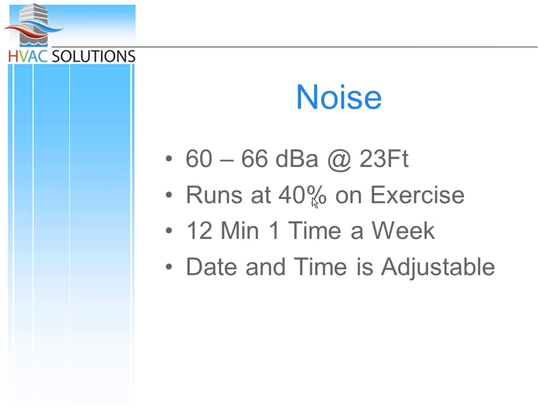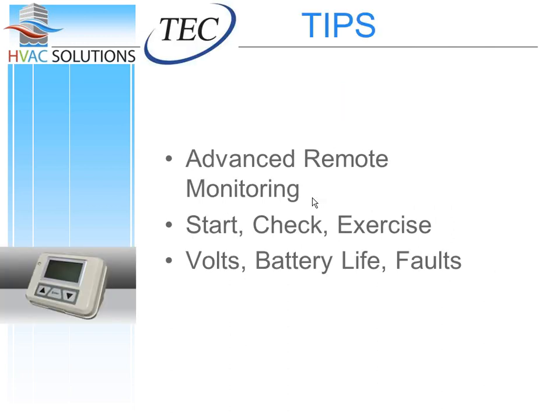When we talk about the noise, I'll tell you, these things sound like a riding lawnmower. They are not quiet. The nice thing is that when they exercise, which is once a week for about 12 minutes, they run at about half capacity, so it's not full blown - it's running at a lower RPM, and you can have it come on when you'd like. It doesn't have to be Sunday at 2 in the morning, you can have it Saturday morning at 10, something like that. So I talked about the 6 different features that make this unit different from what the other guys are offering.